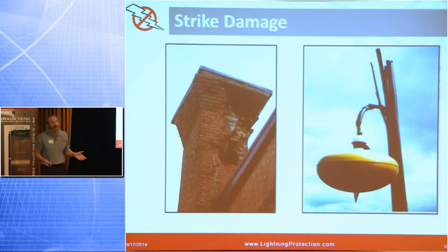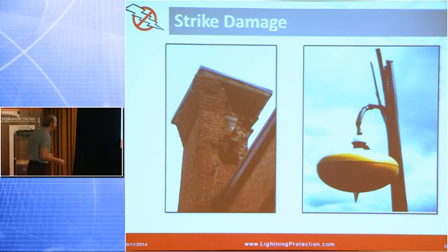For example, on the perimeter of a building, you would need spacing of 20 or 25 feet on the perimeter. So the bigger your building, the more lightning rods you need. You need a certain amount down the middle, 50-foot spacing in the middle, 50-foot spacing between rows for a conventional design. Whereas an ESE says, hey, I can just use one of these and I'll collect everything within 60 meters. Let's say 120 feet or whatever it might be. Or 90 feet.